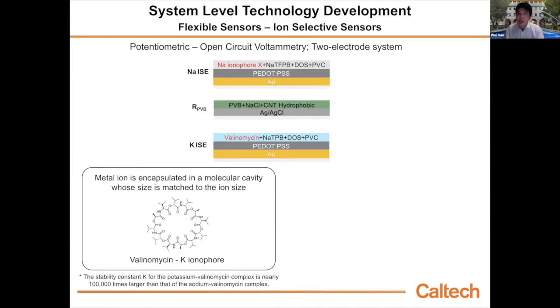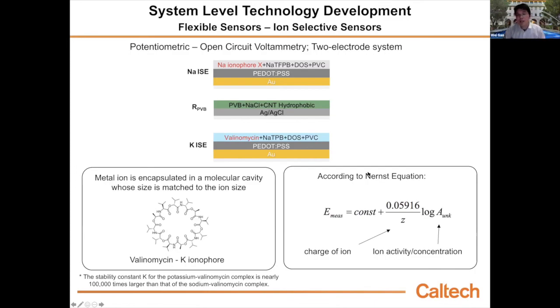If you put this ion selective sensor in a solution containing potassium ion, the ion will enter this ring and set the voltage of the ion selective electrode. We measure the voltage output, the voltage difference between the ion selective electrode and the reference electrode. According to the Nernst equation, the sensitivity is 59.16 millivolts per decade of concentration. The measured voltage has a log-linear relationship with the ion concentration. This is how we monitor ions.